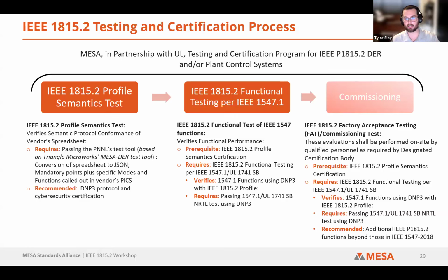And then you get into commissioning. This is your factory acceptance testing. You're going to go through all of the same steps, but you also have to factor in whatever your interconnection agreements, your utility's requirements, your site restrictions. Those all have to be factored in, and it's not a one-stop shop defined standard. It's going to be very specific to individual implementations.